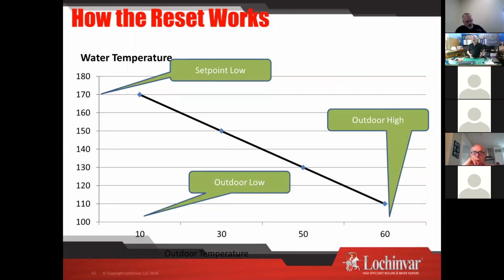Okay. Our outdoor high at 60, I'm going to set that for 110. And this is just some numbers that I picked, random numbers. So at 60 degrees out, 110. What this does is basically at 50 degrees out, I'm running 130 degree water. And at 30 degrees out, I'm running 150 degree water. And that's kind of how that slope works.